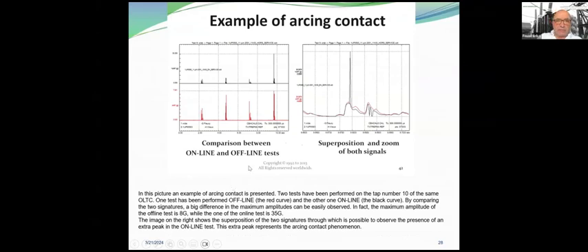In this picture, an example of arcing contact is presented. Two tests have been performed on tap number 10 of the same OLTC. One test has been performed offline, the red curve on the bottom here, and the other one online, the black curve. By comparing the two signatures, a big difference in the maximum amplitudes can be easily observed. In fact, the maximum amplitude of the offline test is 8G, while that of the online test is 35G.